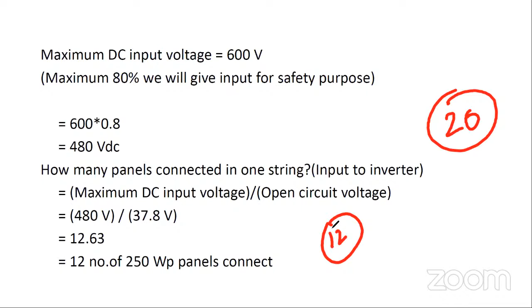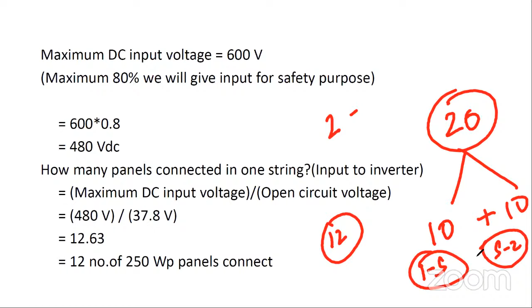But how many panels do we have? 20 panels. The maximum limit of one string is 12. How many strings can we give? 2 strings we can give. Now how are we going to divide? We are going to divide as 10 plus 10. So in the first string, we are going to give 10 panels, and in the second string, we are going to give 10 panels. That is how it is decided.